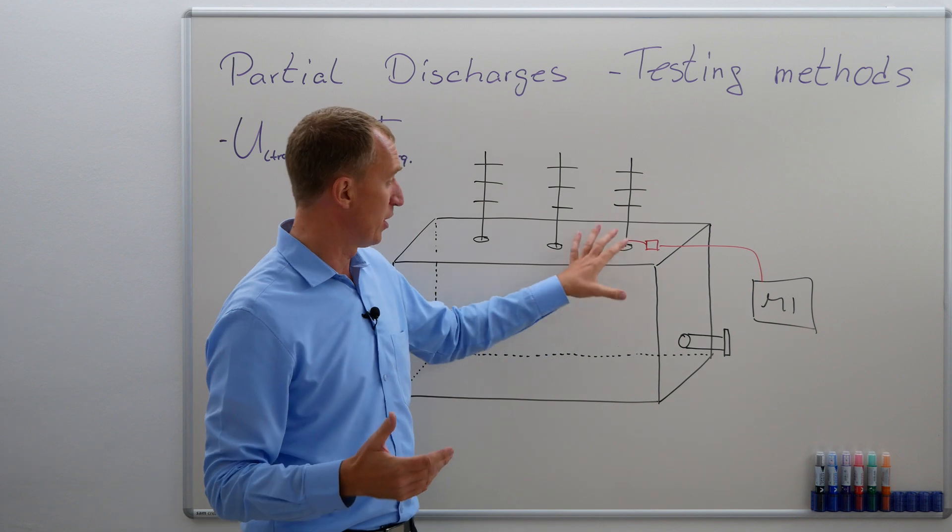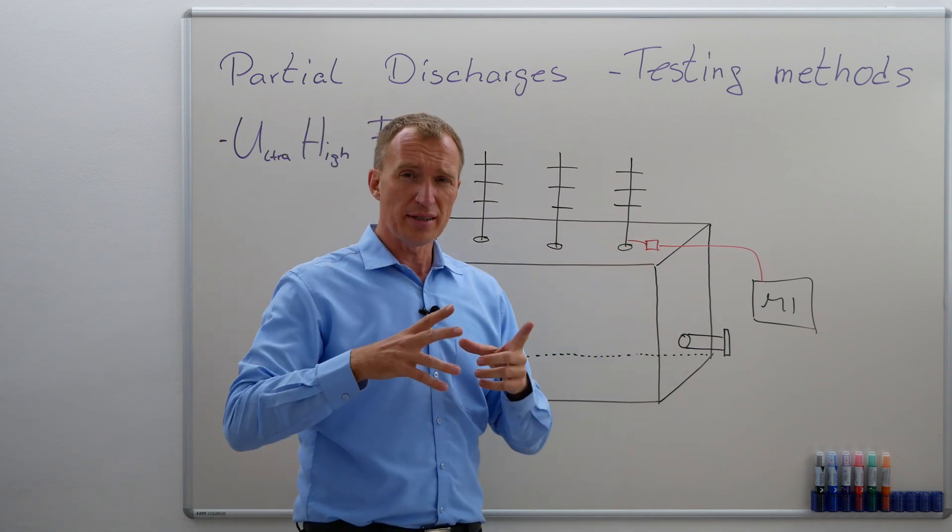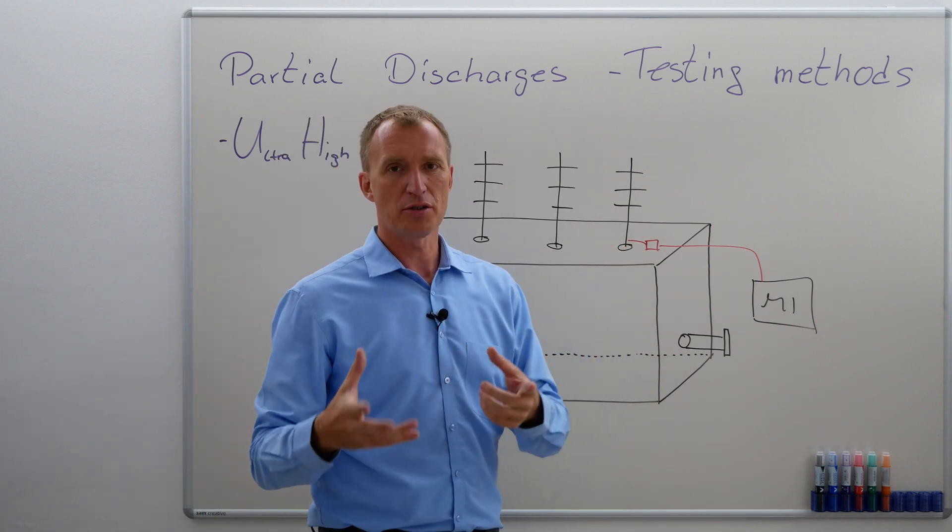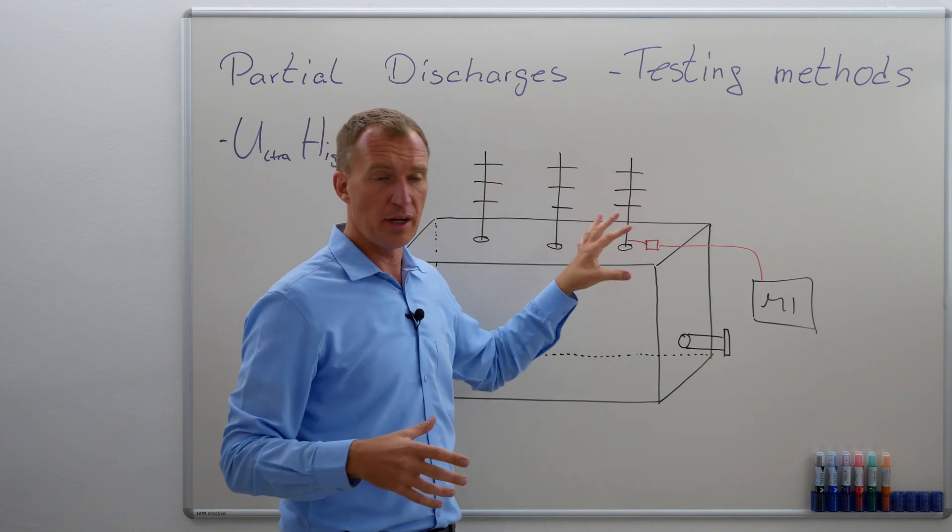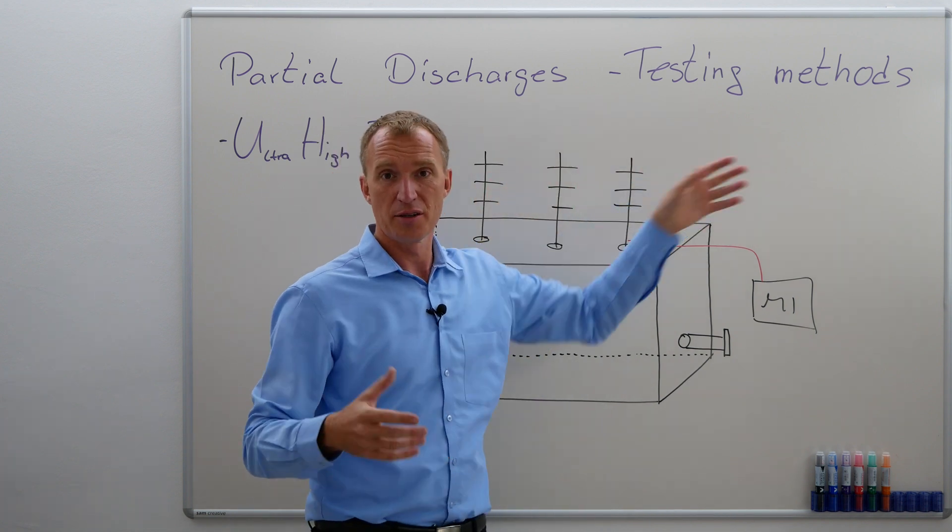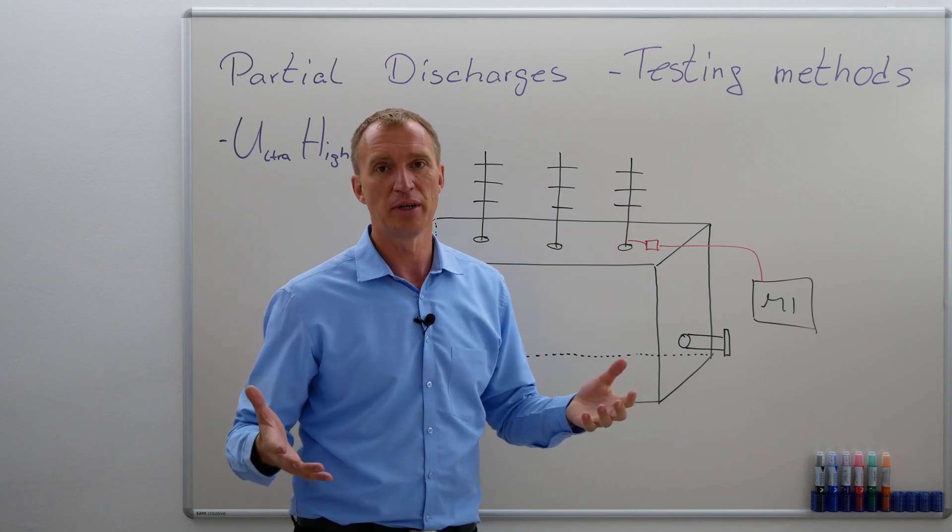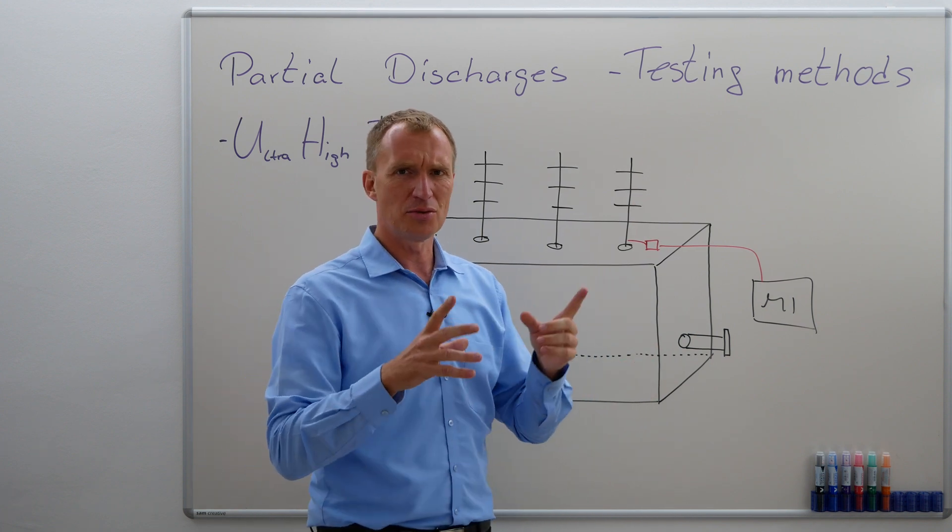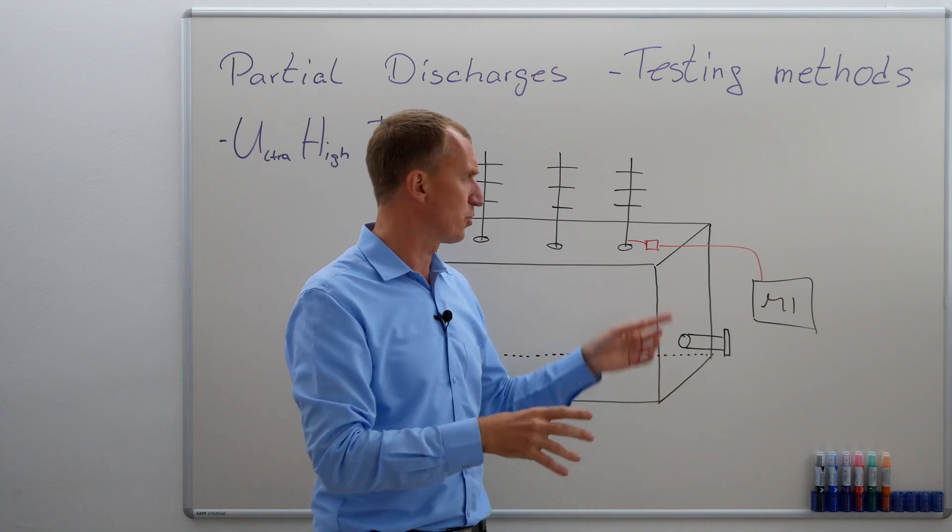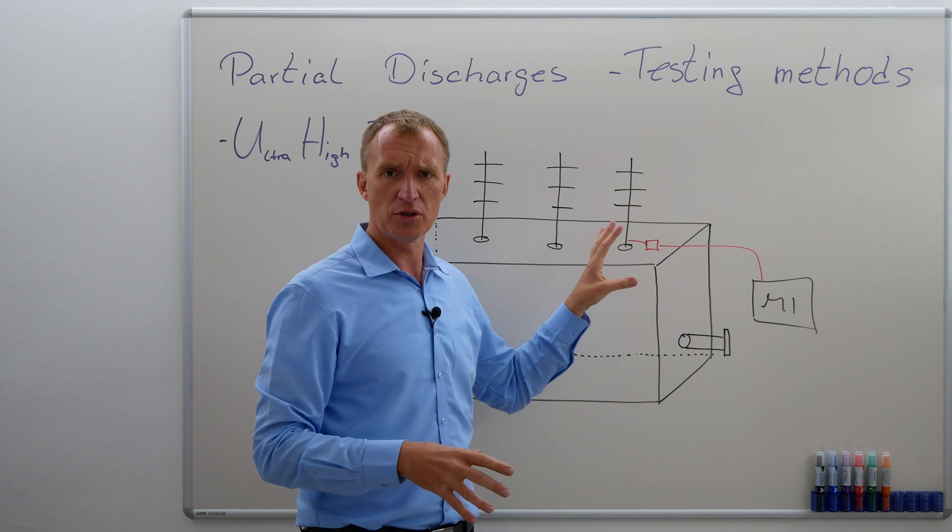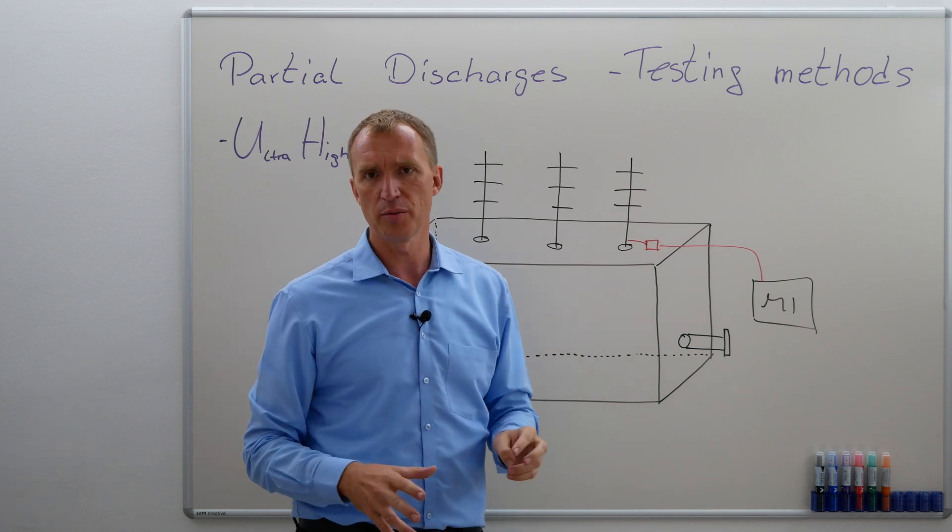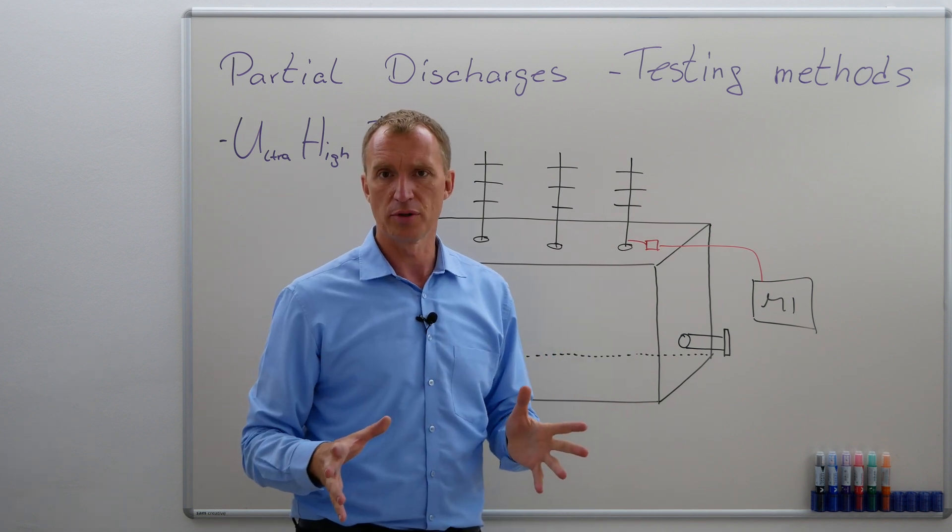We have a small problem. Whenever we are measuring, it's always hard to figure out where is the partial discharge actually coming from. It could come from the bushing, or from one of them, or it could come from outside. The problem is we are not in a shielded room. There are ways to have an idea, do I have a partial discharge very close to my sensor or very deep inside the transformer? But this is a topic for another video.